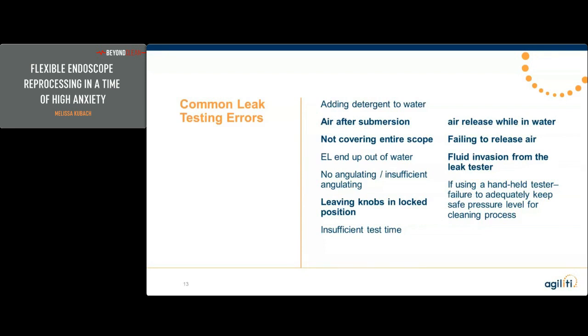Fluid invasion from the leak tester is a horrific event. I had a hospital I went to often, and I was called in because they couldn't get any images in the GI. You could see water in the eyepieces within the urology clinic, and the OR had to cancel cases. Every single department was affected. What it turned out to be, when I came in, is I immediately saw the leak tester tubing hanging in the water when I walked into the department.